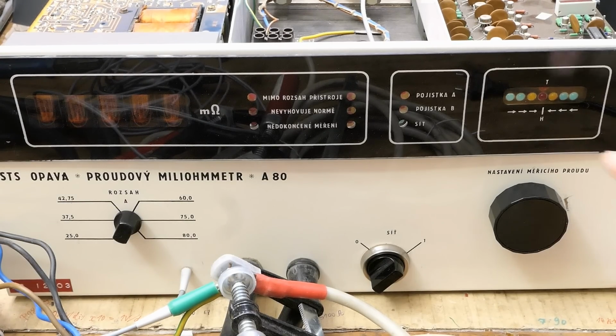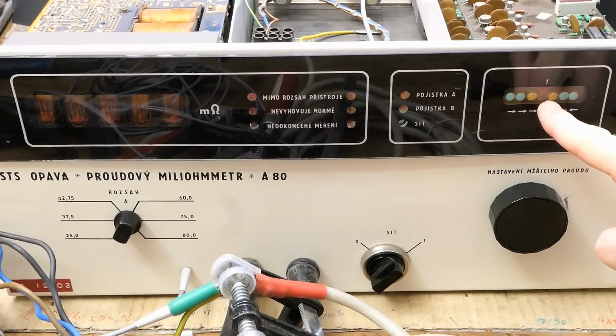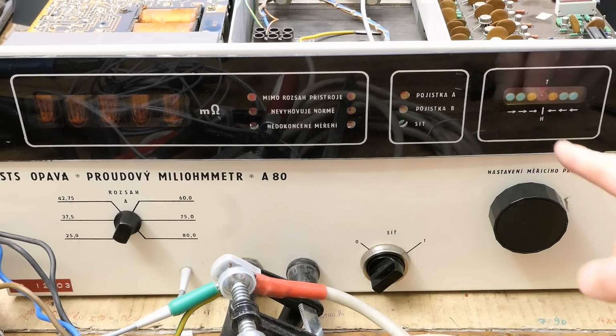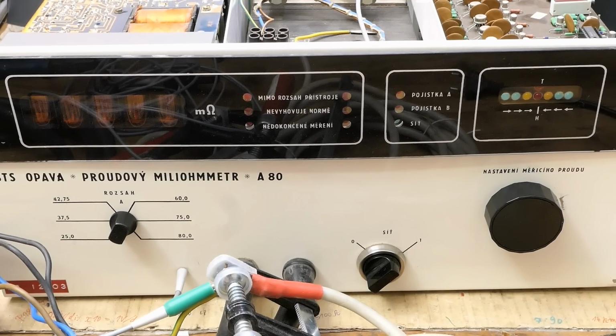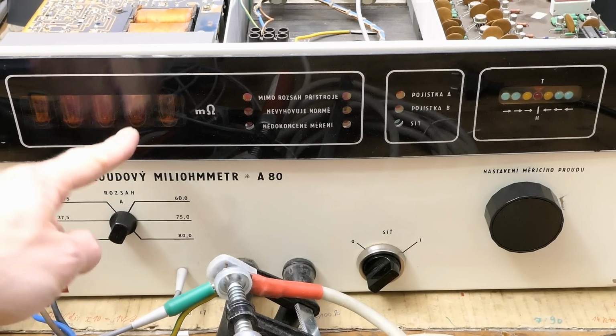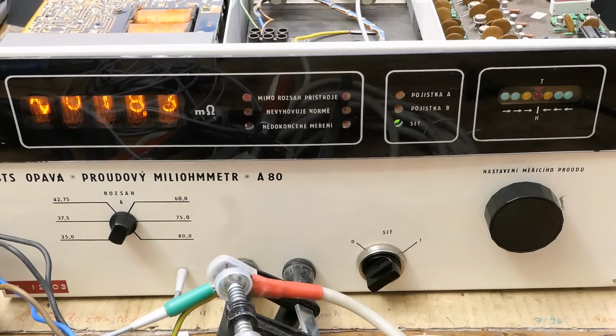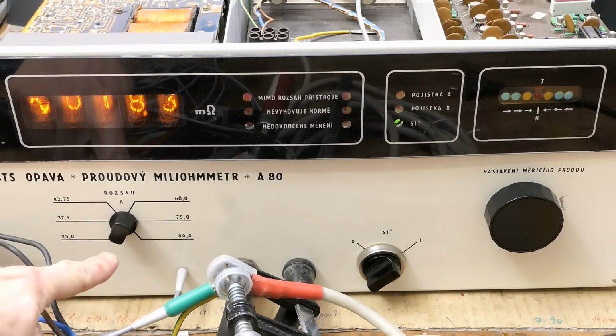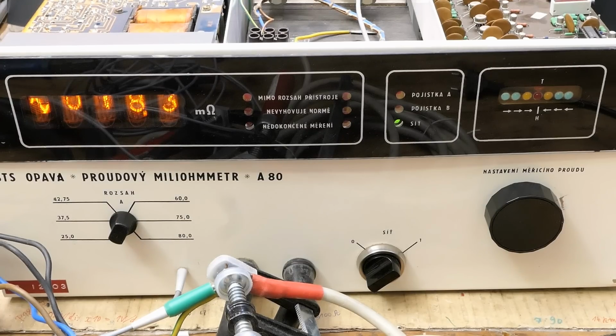It really just tells you how to set the variac using this scale, which is sort of logarithmic, much more sensitive in the center. So you can set it with some sort of precision. You basically set the right current and this just measures the voltage drop on the measured resistance. And the machine is now working, and this switch is permanently set to 25 amps. It's usable, but I don't have much use for it.